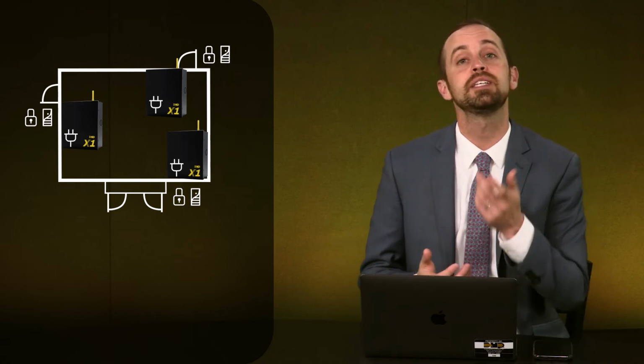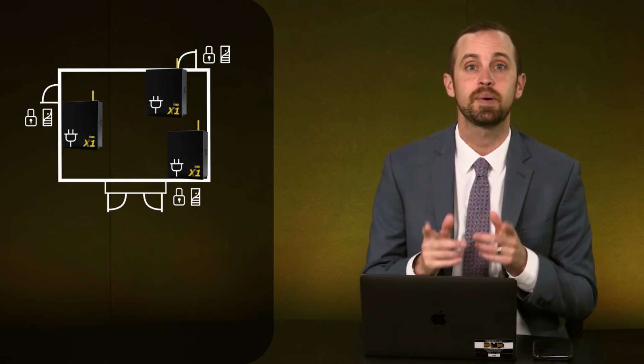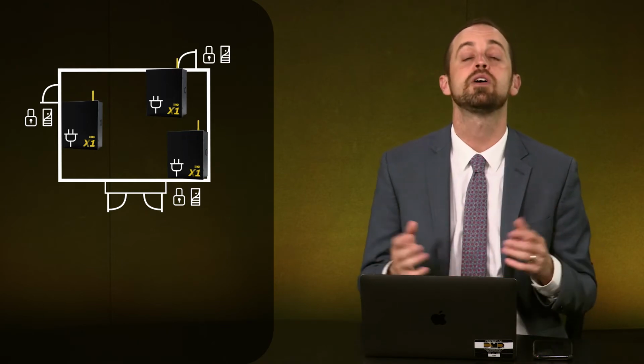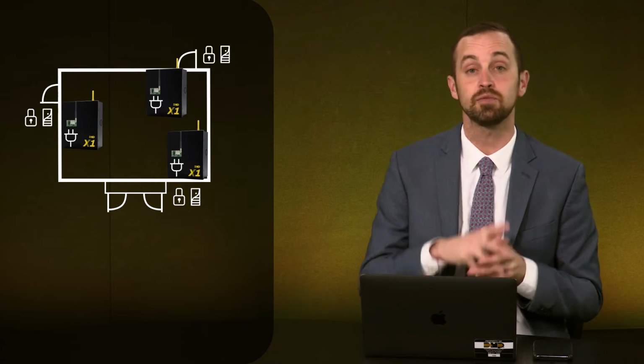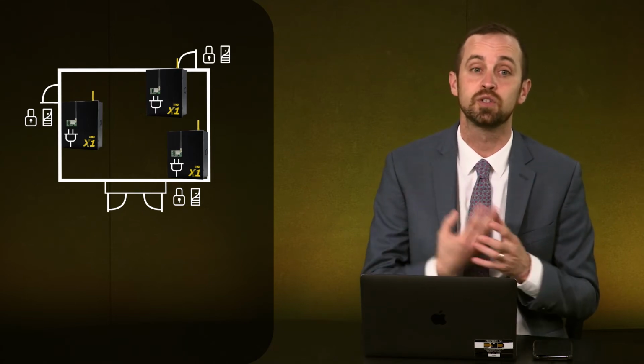Remember that if PoE is available, you can use a PoE module that is available from DMP to power both the X1 and provide power to the door hardware. And then we also have the option of cell. So if you're going to use a cellular communicator, remember that you do need one in this example for all 3 doors.